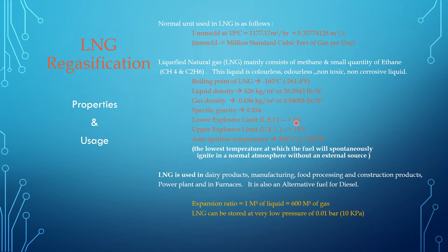The lower explosive limit of LNG or natural gas is 5%, and the upper explosive limit is 15%. The auto-ignition temperature is 595 degrees centigrade, or 1103 degrees Fahrenheit. The auto-ignition temperature is the lowest temperature at which the fuel will spontaneously ignite in a normal atmosphere without an external source. When the gas is heated to 595 degrees centigrade, it will ignite automatically without any ignition source.